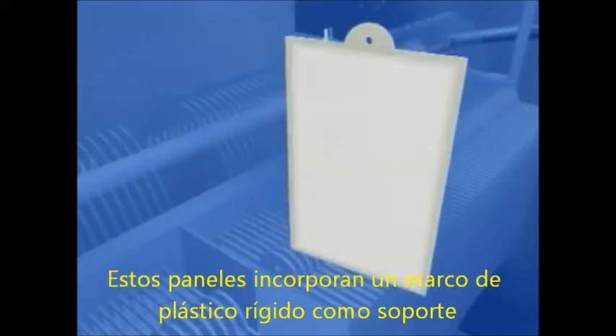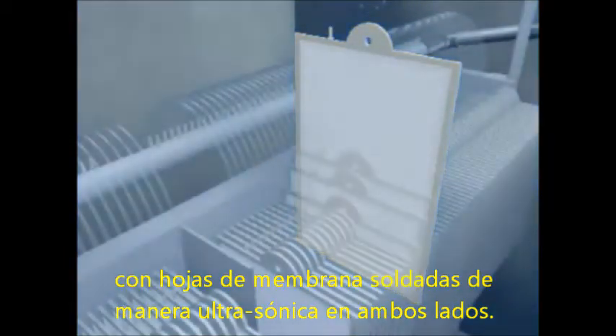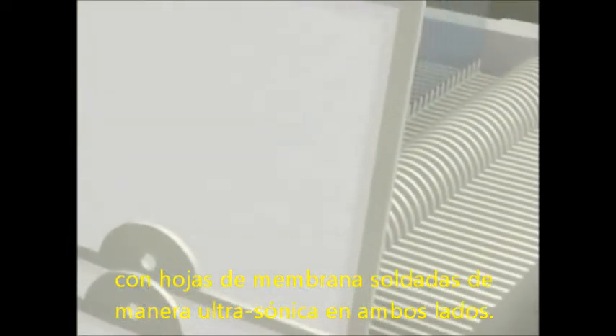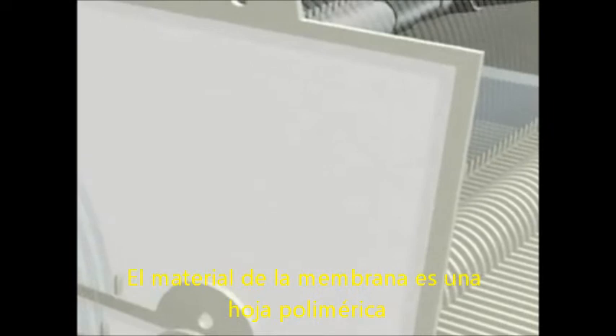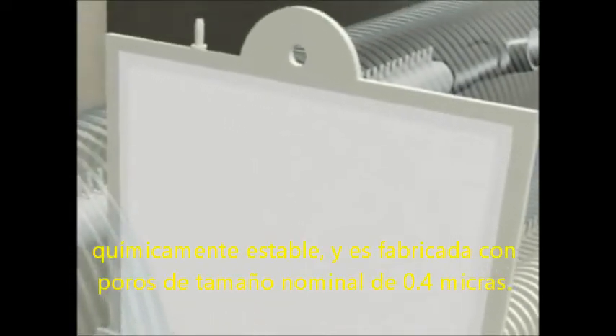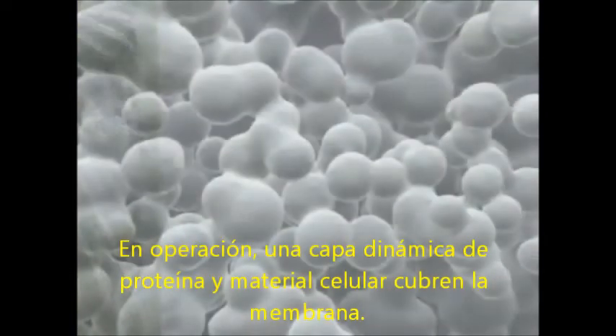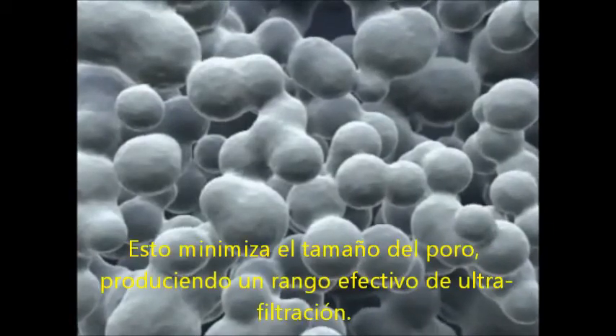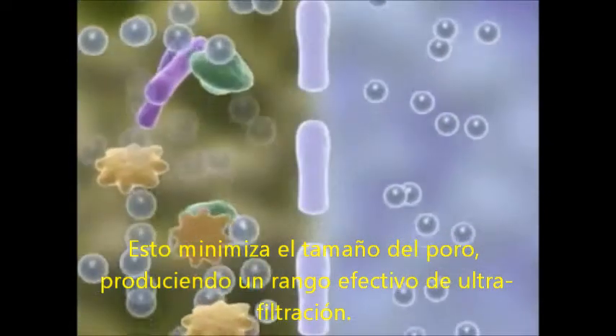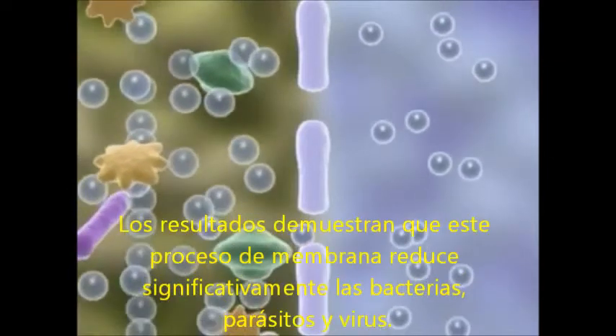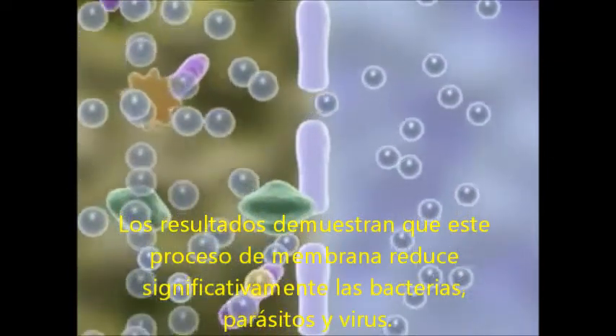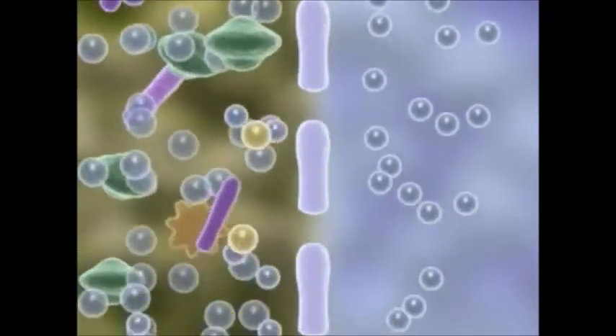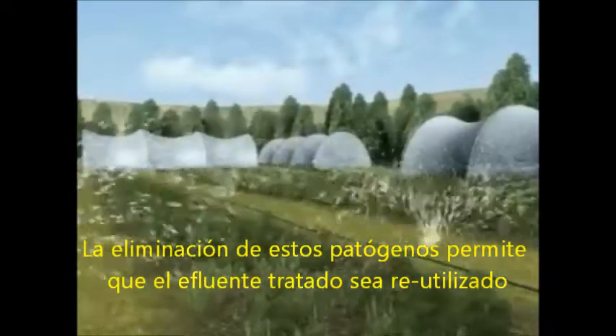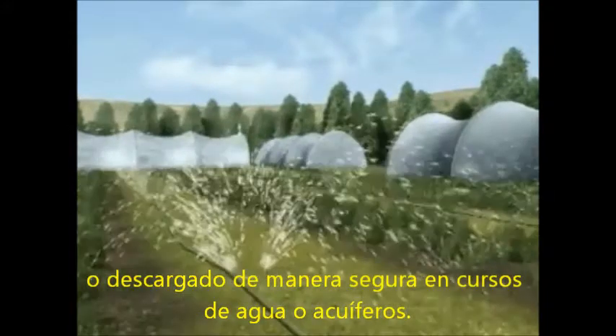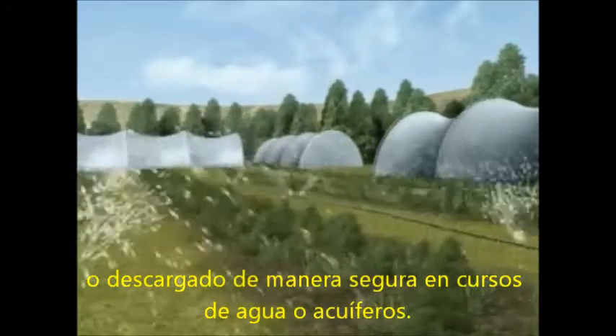The integral part of any membrane bioreactor plant, irrespective of its size, is the membrane panels. These panels incorporate a rigid plastic frame as support, with ultrasonically welded membrane sheets on either side. The membrane material is a chemically stable polymeric sheet and is manufactured with a nominal pore size of 0.4 microns. In operation, a dynamic layer of protein and cellular material covers the membrane. This minimizes the pore size, producing an effective ultrafiltration range. Results show this membrane process significantly reduces bacteria, parasites and viruses. The removal of these pathogens enables the treated effluent to be reused or safely discharged into watercourses or aquifers.